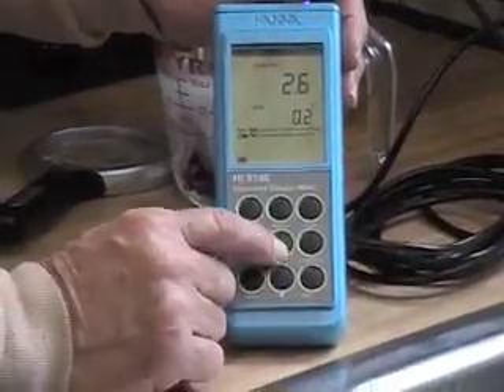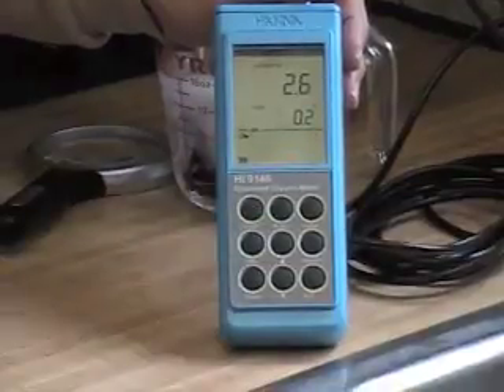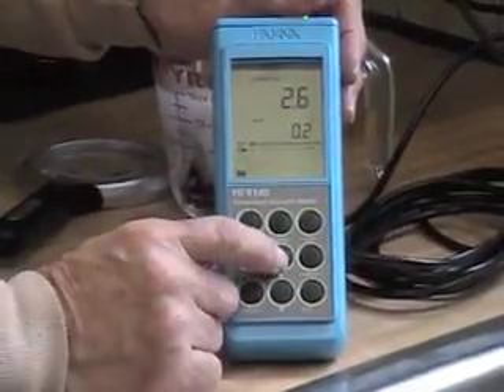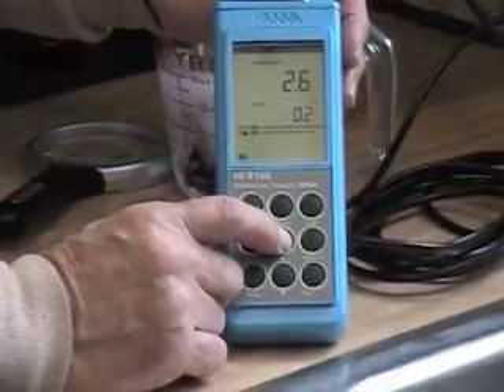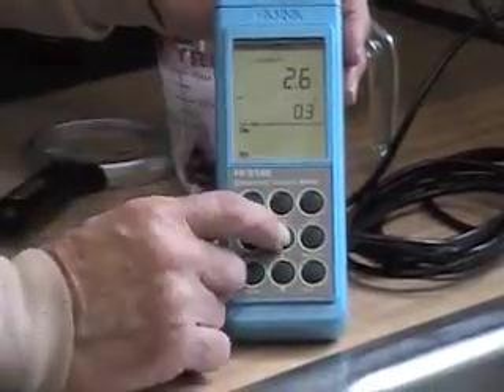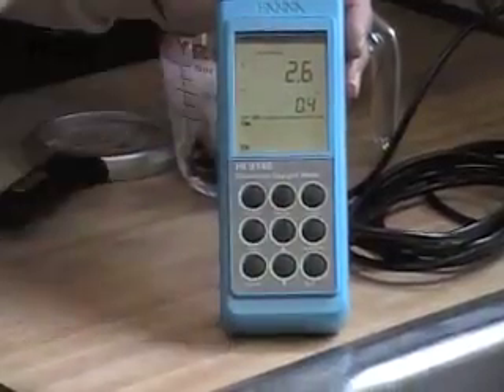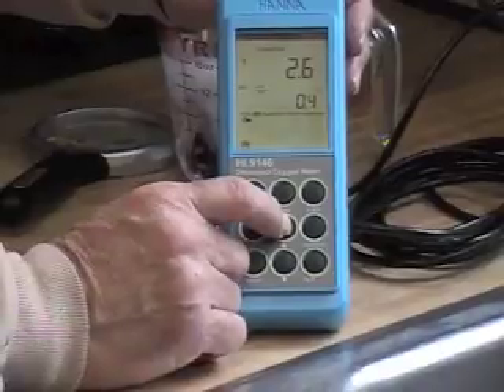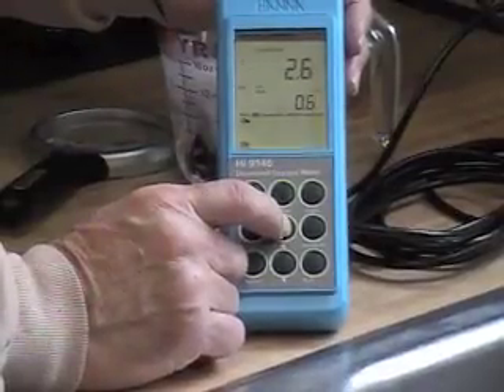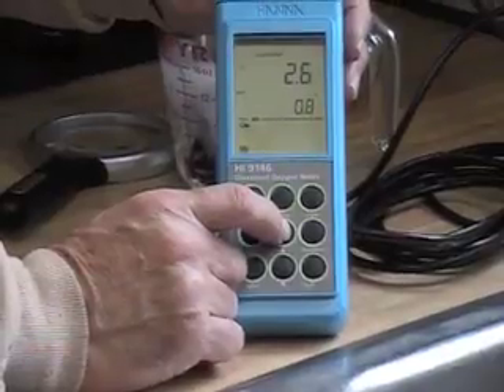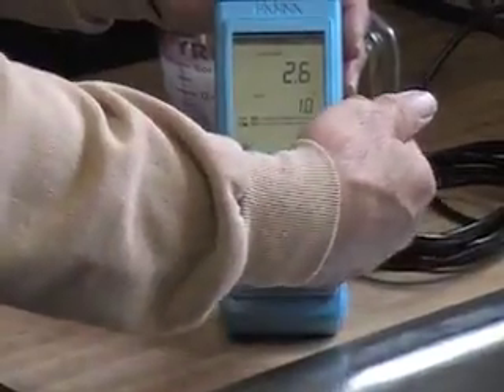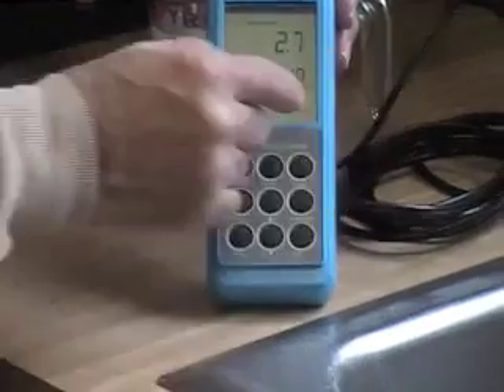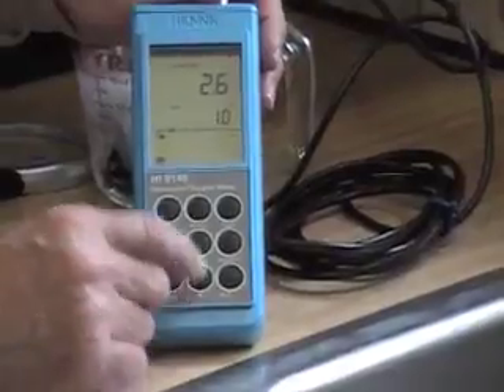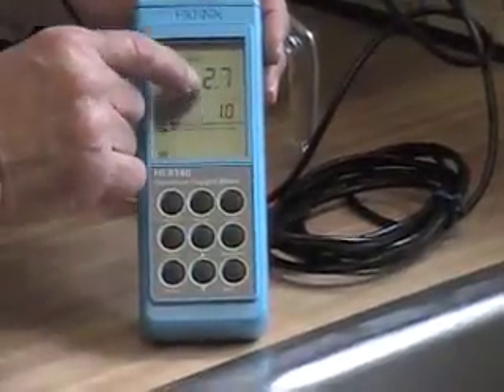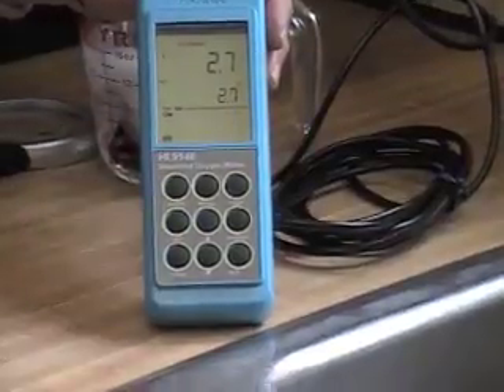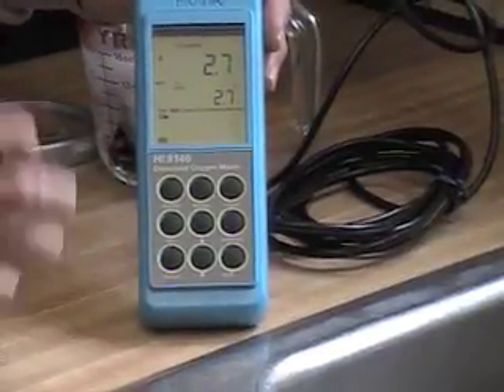So I'm just going to use my arrow buttons, and you can't do this real fast. I've actually seen the meter shut off if you try to move too fast. So just very carefully, you can see I'm incrementing up to 0.3, 0.4, and then you let it do that. It'll blink once in a while. Don't go too fast. Let it do its blinking. And there, when you're in normal mode, your degrees C temperature is over here on the lower right hand side display under the dissolved oxygen number, and you're trying to get this number now to match the number above. So there we're matching at 2.7 degrees, and I'm going to settle for that.